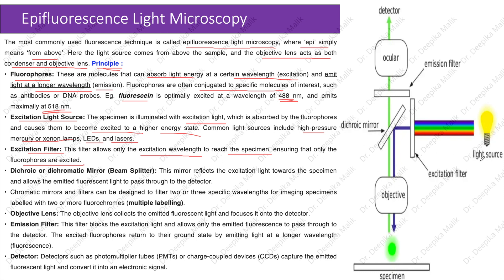As you can see in the diagram, light from the source hits the excitation filter and only light of a specific wavelength is allowed to pass to the specimen, which is labeled with a certain fluorophore. The dichroic or dichromatic mirror (beam splitter) reflects the excitation light towards the specimen and allows the emitted fluorescent light to pass through to the detector.